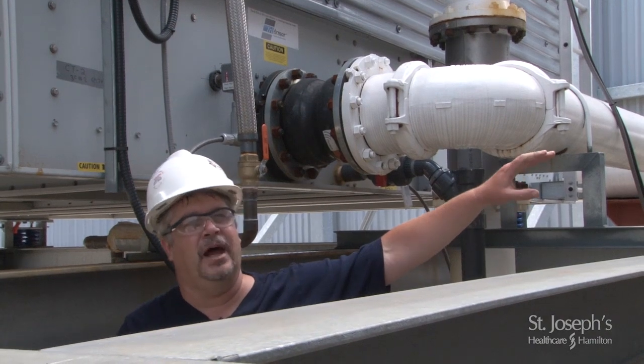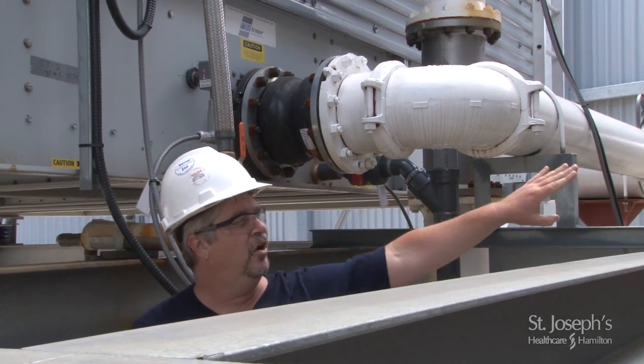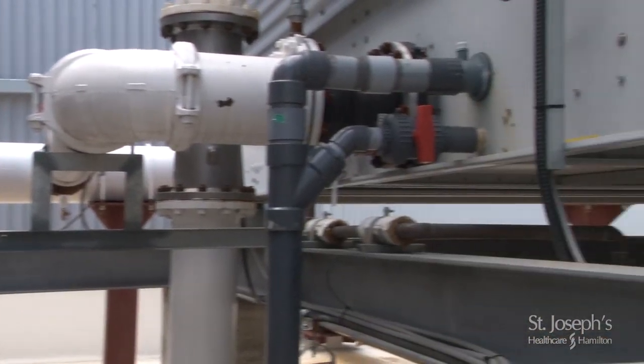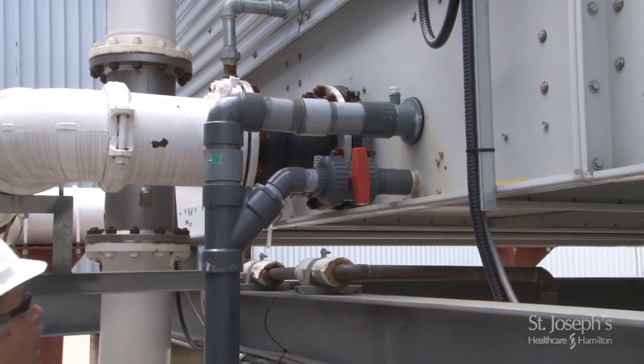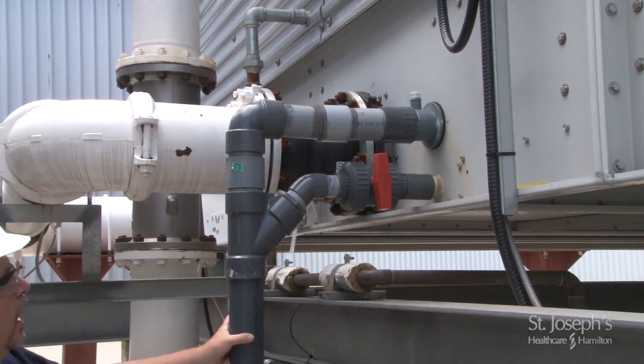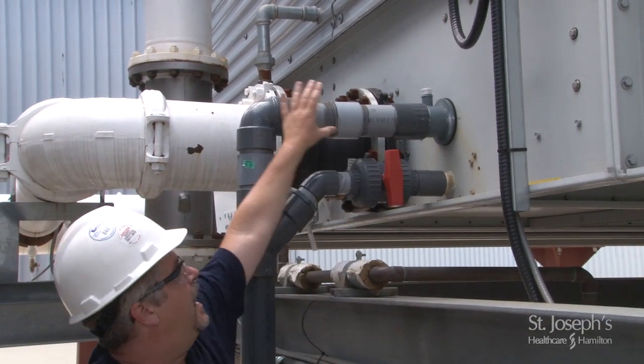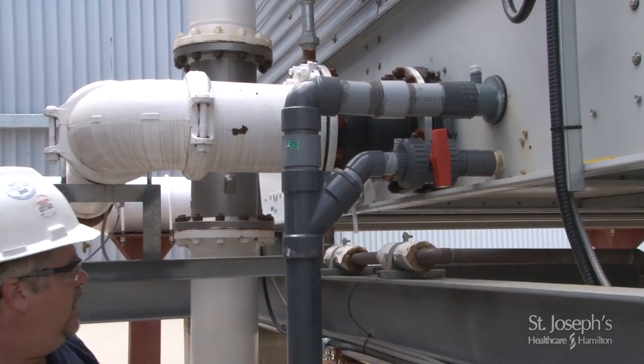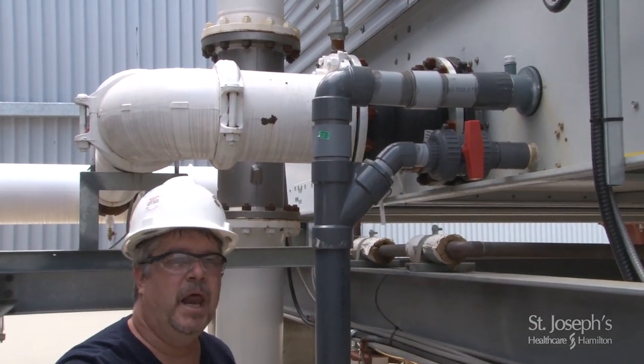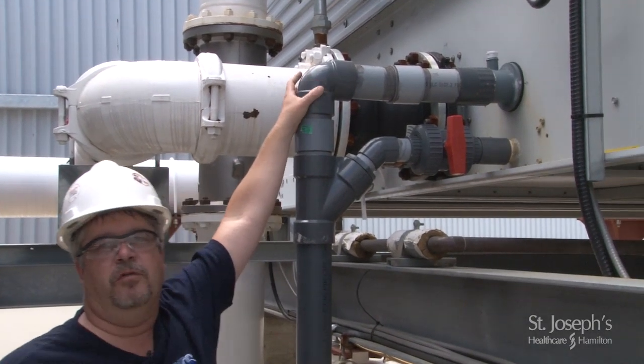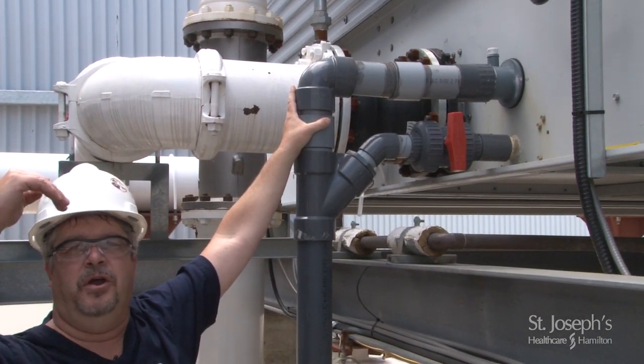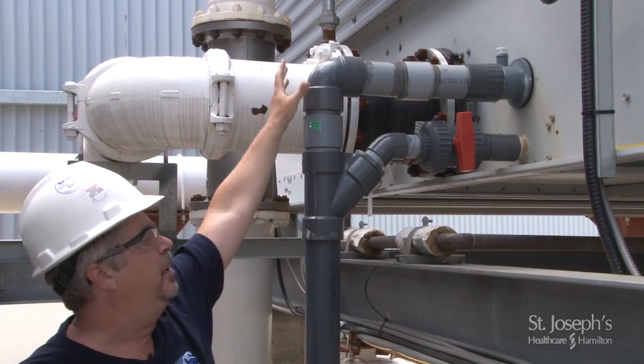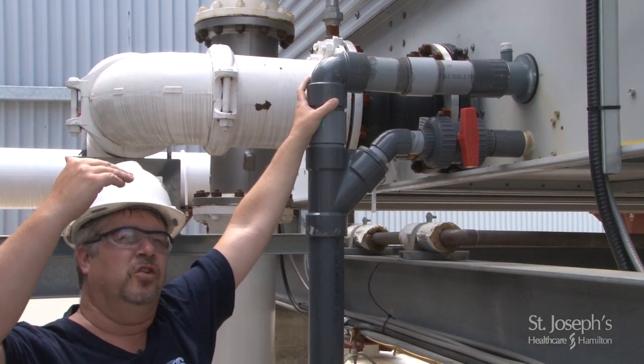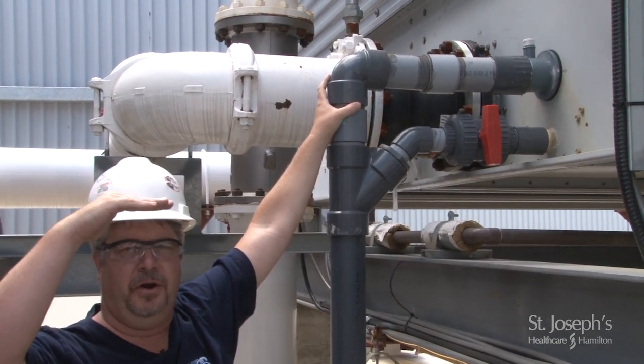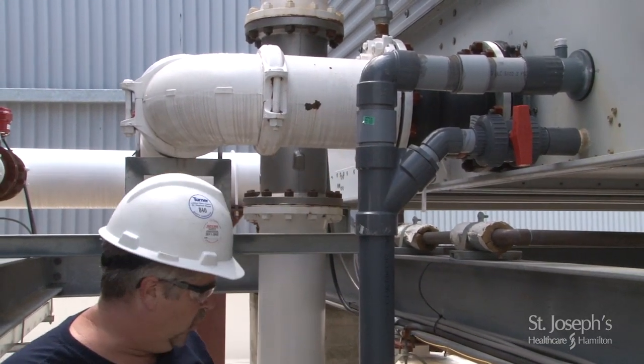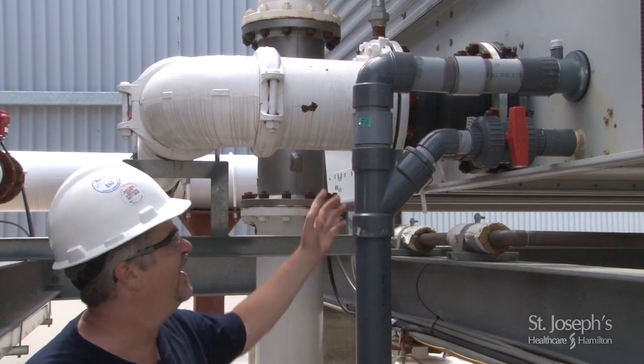I'm going to take you over to this tower, as these 3 towers are identical, and it's a little easier to see from our vantage point. You have 2 gray pipes coming out. One has a shut-off valve on it, and the other just goes straight into the tower. These pipe down to drain. The top one is your overflow connection. Inside the tower, there is a set height where this pipe is piped in. If the tower ever reaches a critical level of water, it will just start overflowing and running that water down to drain.